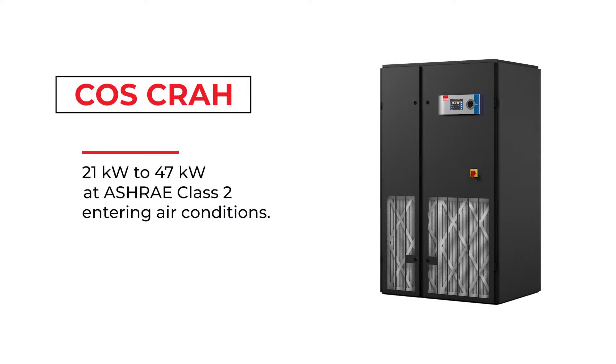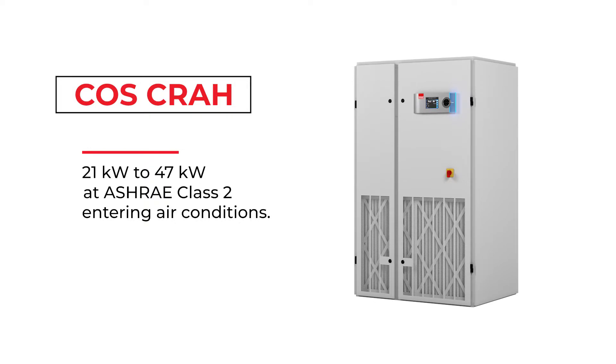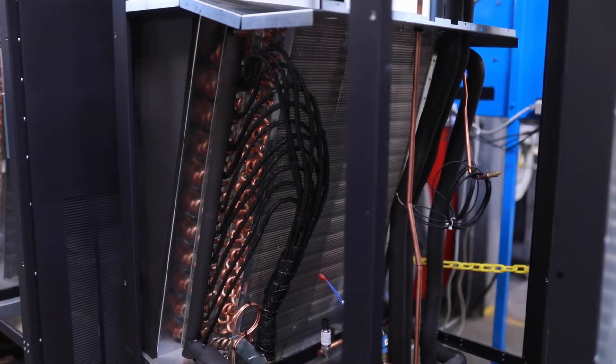COS CRAHs are designed with high-efficiency electronically commutated fans to provide reliable airflow while using very little energy. The COS CRAH units are available in capacity increments from 21 kW to 47 kW at ASHRAE Class II entering air conditions. They are constructed with energy-efficient electronically commutated fans, high-pressure control valves, and coils designed to have optimal heat transfer with a low total head loss.